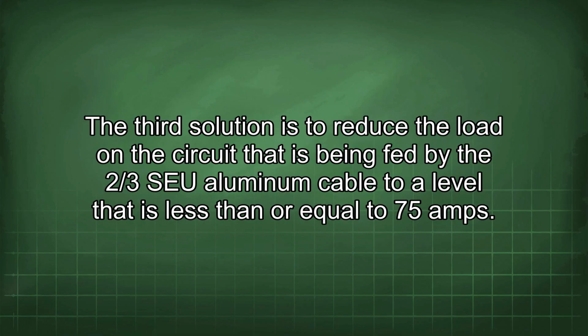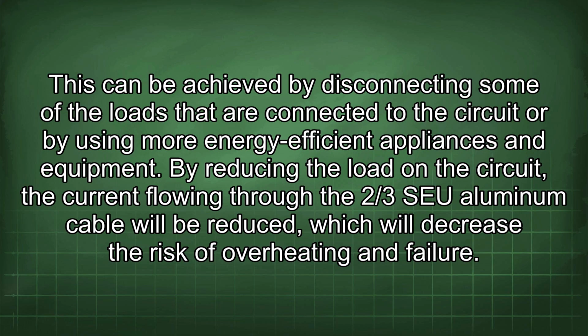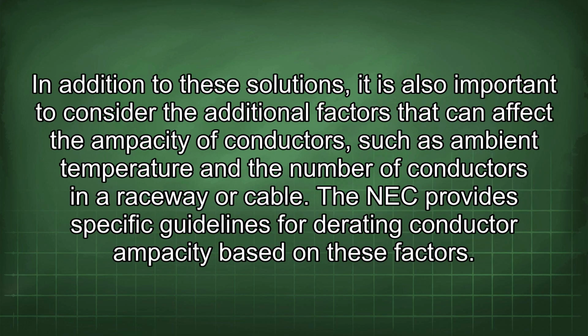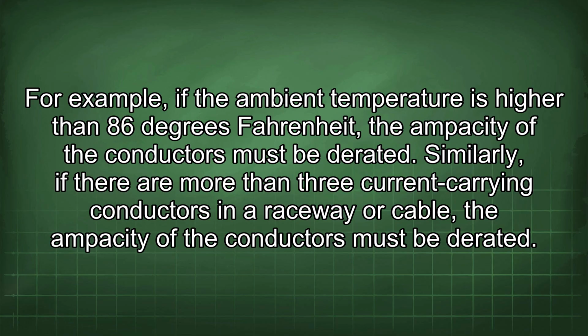The third solution is to reduce the load in the circuit that is being fed by the 2/3 SEU aluminum cable to a level that is less than or equal to 75 amps. This can be achieved by disconnecting some of the loads that are connected to the circuit or by using more energy-efficient appliances and equipment. By reducing the load in the circuit, the current flowing through the 2/3 SEU aluminum cable will be reduced, which will decrease the risk of overheating and failure. In addition to these solutions, it is also important to consider the additional factors that can affect the ampacity of conductors, such as ambient temperature and the number of conductors in a raceway or cable. The NEC provides specific guidelines for derating conductor ampacity based on these factors. For example, if the ambient temperature is higher than 86 degrees Fahrenheit, the ampacity of the conductors must be derated.